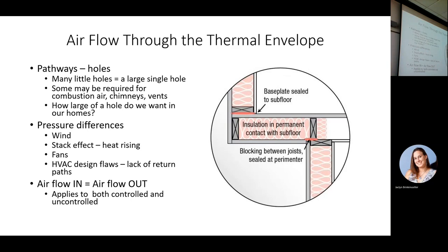If your house is real tight and you put in that 1000 CFM range hood, it's not going to move 1000 CFM because it can't get the air into the space. If you have a B vent, an 80% furnace, and/or a water heater hooked to it, and you have that 400 plus CFM fan in there, where's it going to get air? Down the B vent. And it'll do it all the time. In fact, that's the reason that requirement was put in the code, because we're reversing B vents and all the products of combustion from a furnace and water heater are coming into your house rather than going out the B vent.